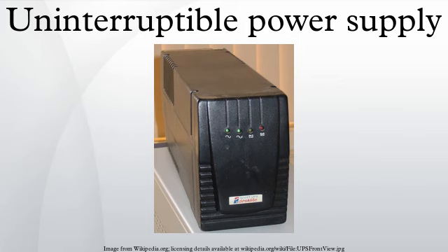Communication. Power management requires the UPS to report its status to the computer it powers via a communications link such as a serial port, Ethernet and Simple Network Management Protocol, GSM GPRS or USB, a subsystem in the OS that processes the reports and generates notifications, PM events, or commands an ordered shutdown. Some UPS manufacturers publish their communication protocols, but other manufacturers use proprietary protocols.